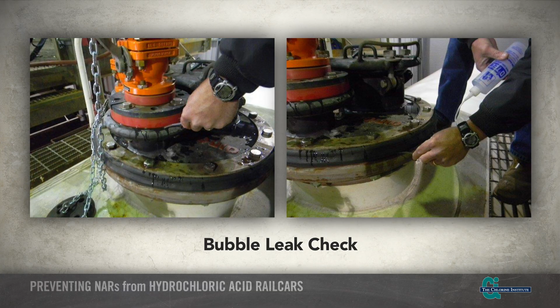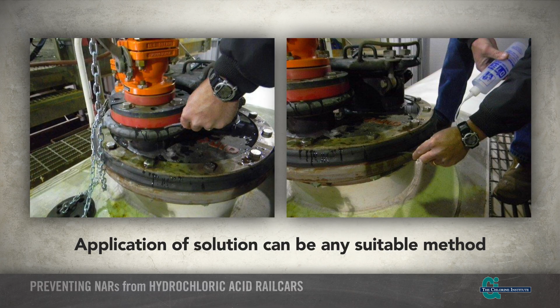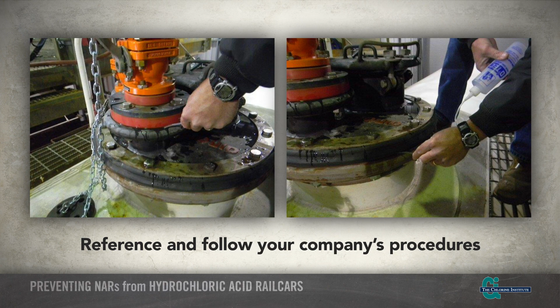Using a bubble leak solution is a slightly different application method than using aqua ammonia. In general, the bubble leak solution can be applied in any suitable way. Be sure to reference and follow your company's bubble leak test procedures. There are many acceptable commercial-grade solutions on the market to use for bubble leak testing. Here are some products currently used in the industry.